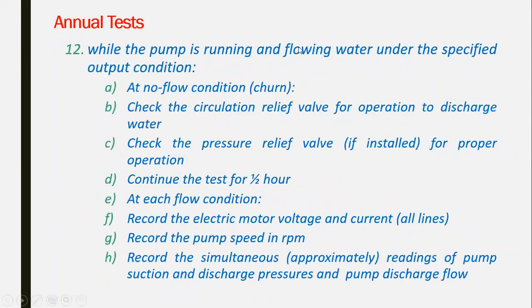While the pump is running and flowing water under the output condition, and at the no flow condition, we have to take all the readings. In the no flow, or shutoff, situation, check that the circulation relief valve for the electric pump is discharging to prevent damage to the casing of the pump. Check the pressure relief valve, if installed, for the diesel pump. Continue the test for at least half an hour at each flow condition, conducting the test and taking the readings, with observation of the circulating valve and the pressure valve, etc.